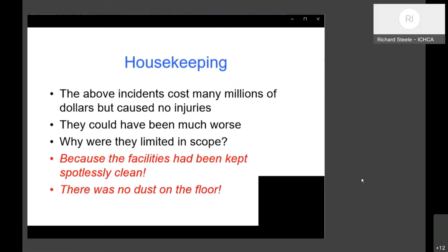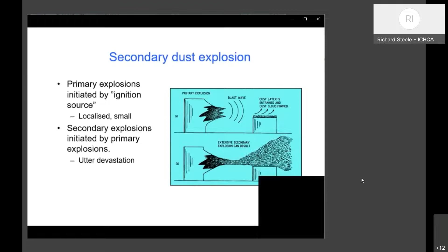If you look at dust on the floor, this is the biggest hazard that turns a small event into a catastrophe. A small ignition with a little blast may cause localized damage. But if there's dust on the floor, that dust gets thrown into the air, ignites, and generates a fireball that travels through the whole area. That's called a secondary explosion. Thanks to my friend Dave Price for that diagram.